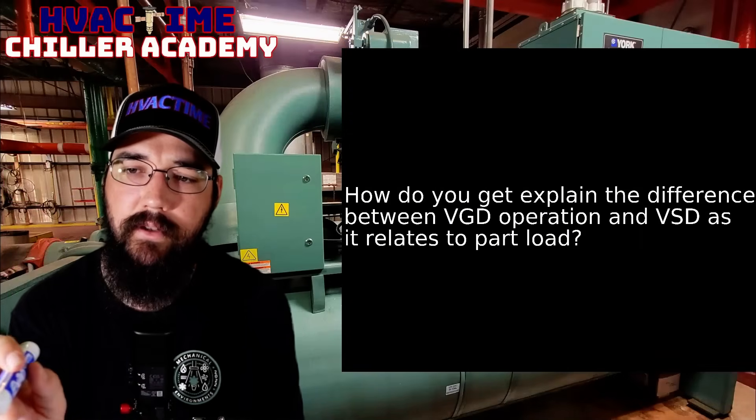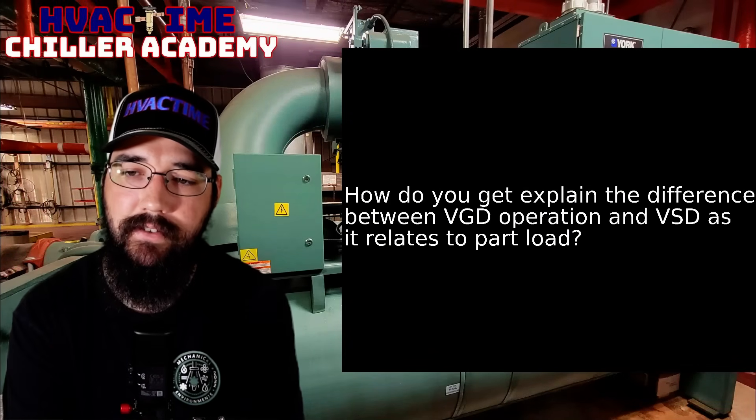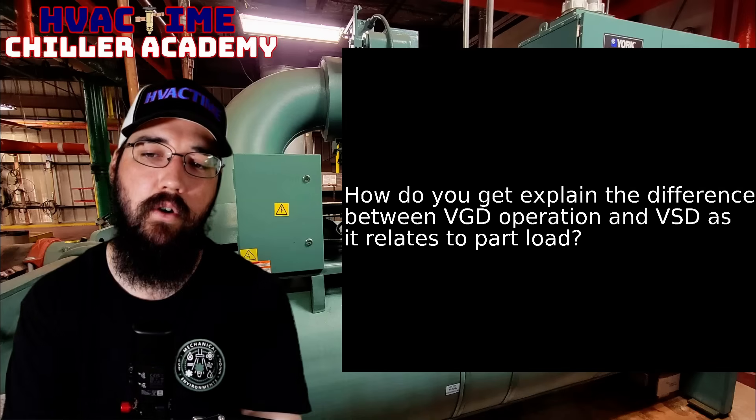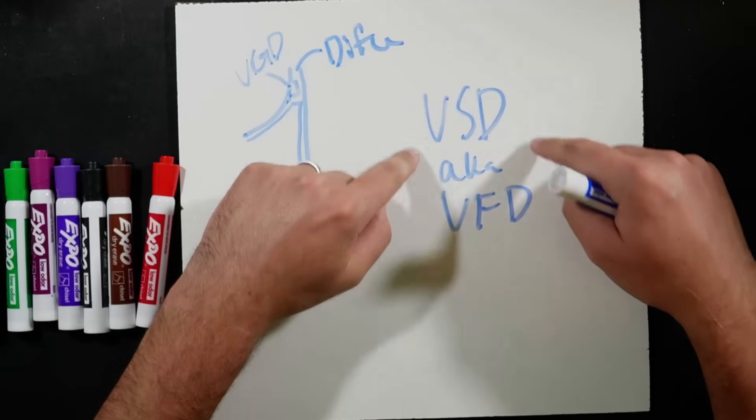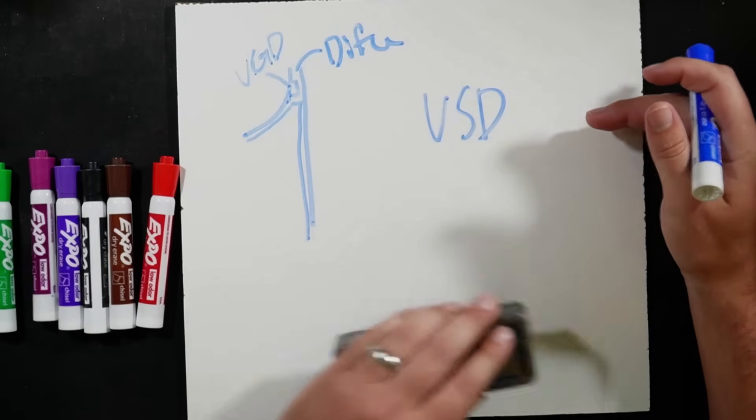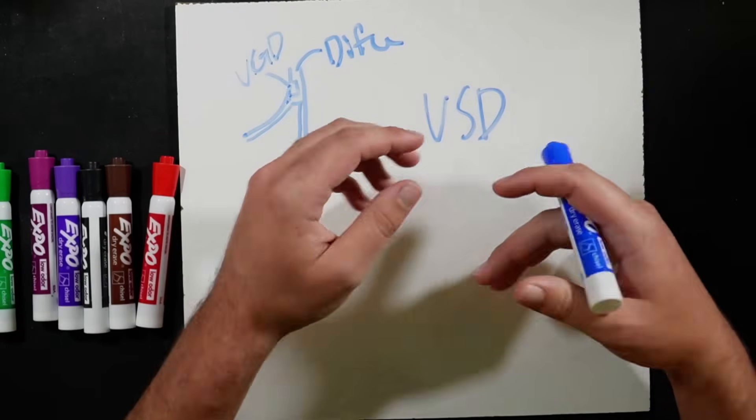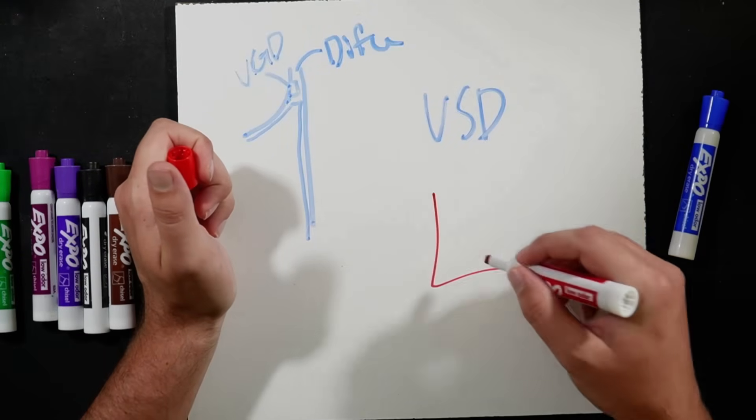How do you explain the difference between VGD and VSD operation in a part load condition? Part of what we can do with the VSD first, we're going to slow the compressor down as much as we can. Now we still have a surge curve to worry about.